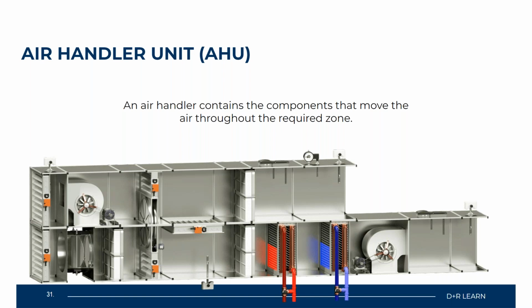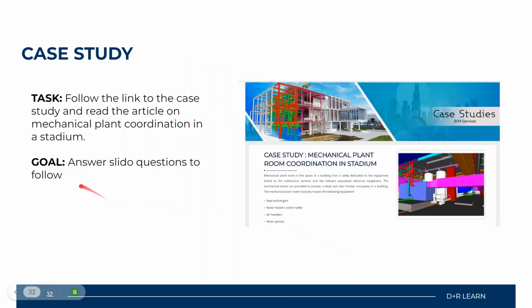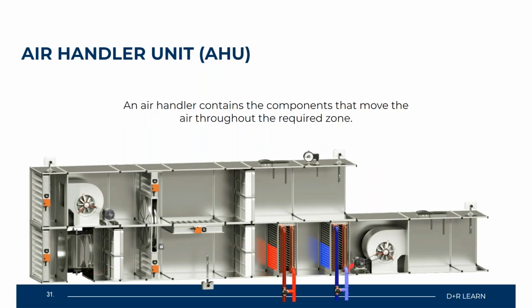So you will have a supply blower, which I'll show you here. Here's your supply blower. So that is connected to a motor system down here. Let's go back, apologies. You have a motor system down here that is able to turn a squirrel cage in here that is able to blow out the air to the different spaces that it is needed. And then you also have a return blower. And what's important about this return blower, which has a motor here, is that it is removing the used air. So all the air, that CO2 that's now left in the space, is being removed by our return air system on our air handler unit.